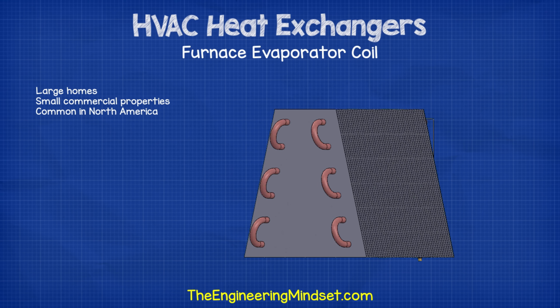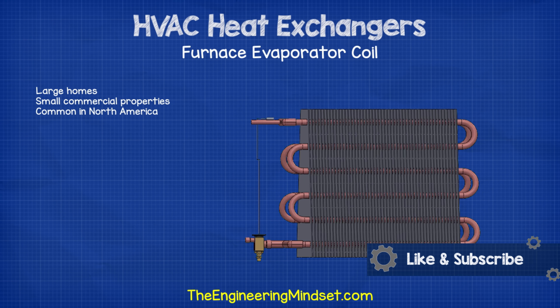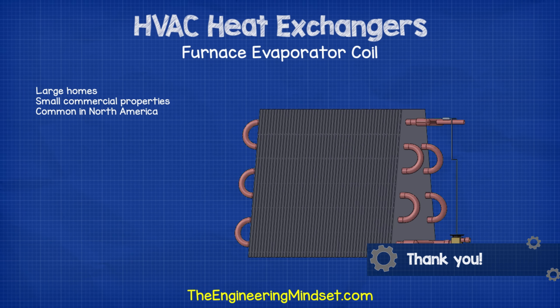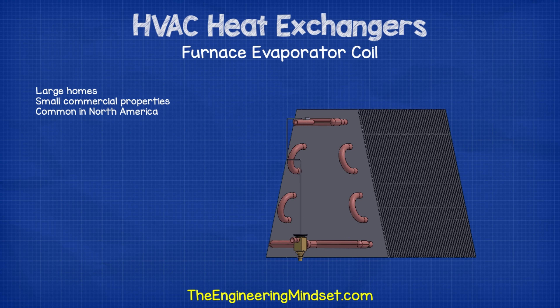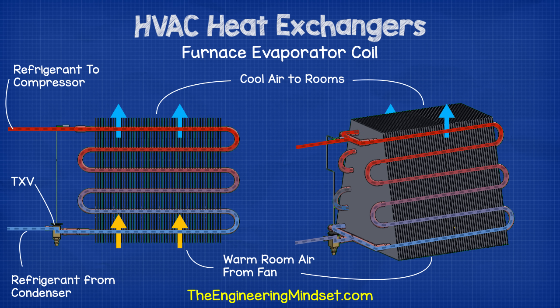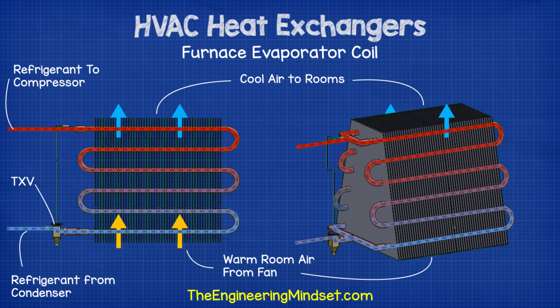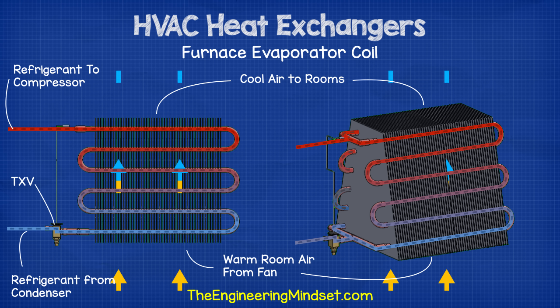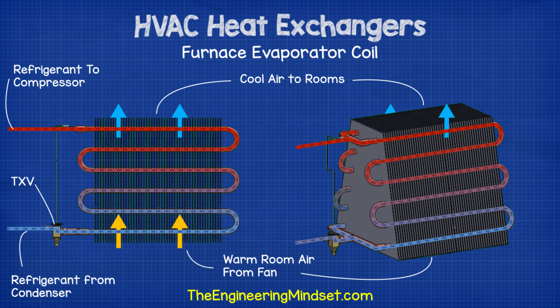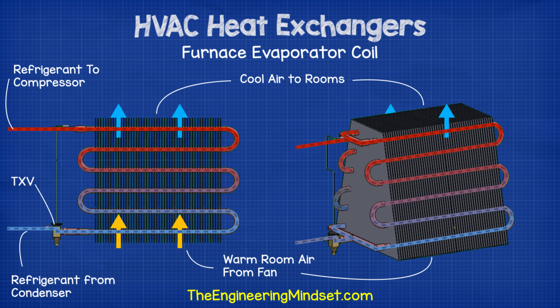Furnace evaporator coils are commonly found in large homes and small commercial properties with small ducted systems. The coil works the same as a thin tube heat exchanger, using refrigerant on the inside with ducted air on the outside. The air passes across the tubes and transfers its heat via forced convection, which is then transferred through the tube wall by conduction. The refrigerant on the inside carries this heat away through forced convection, then boils and evaporates away to the compressor.